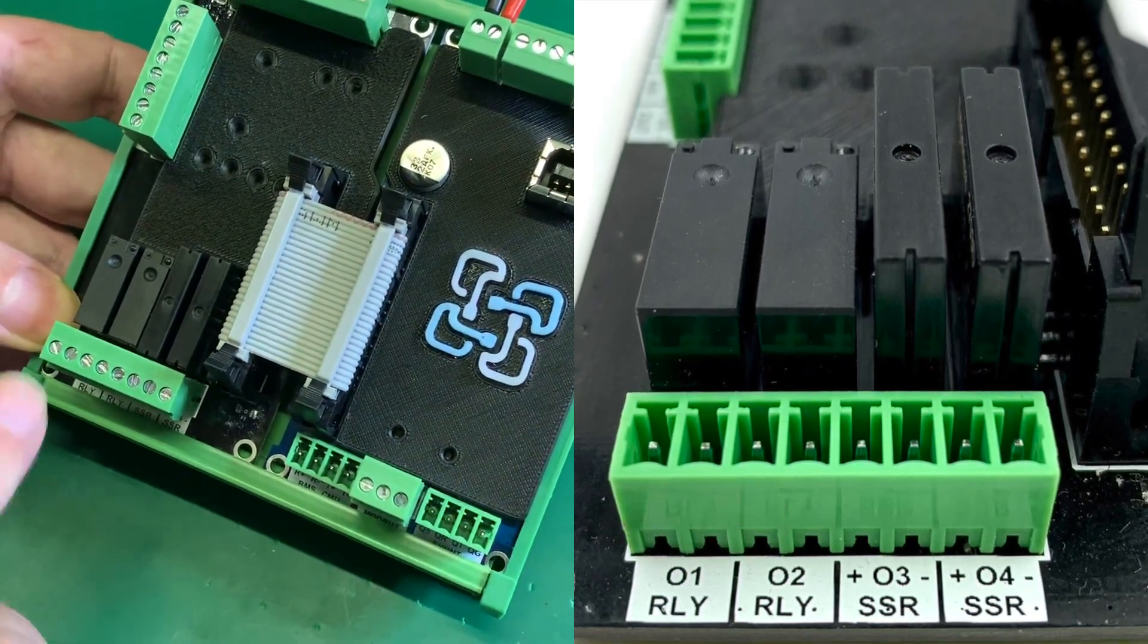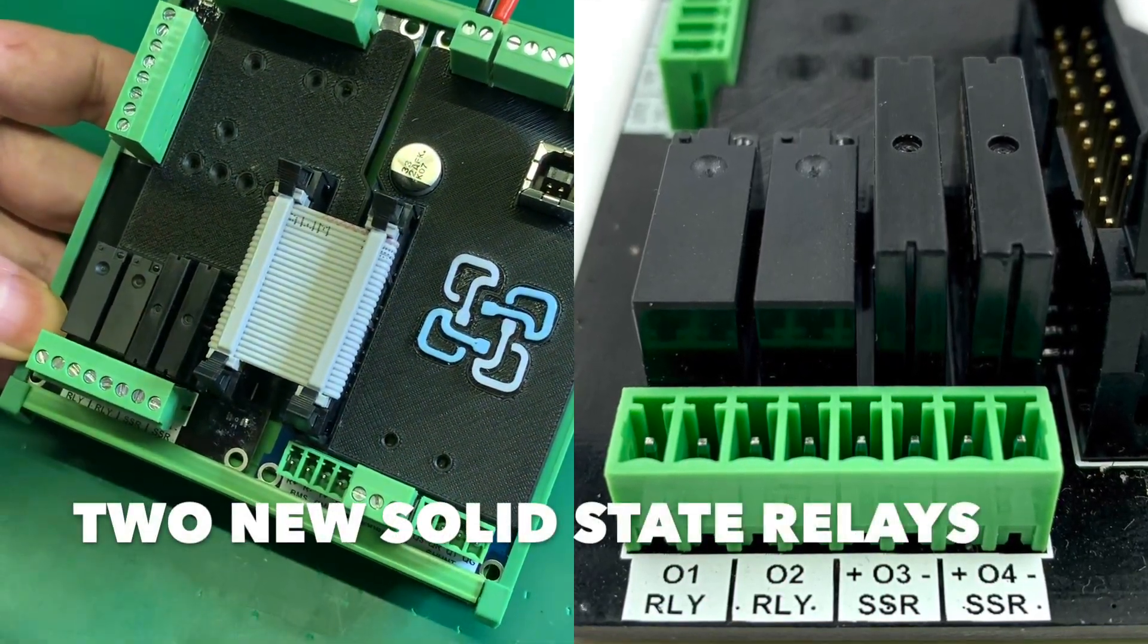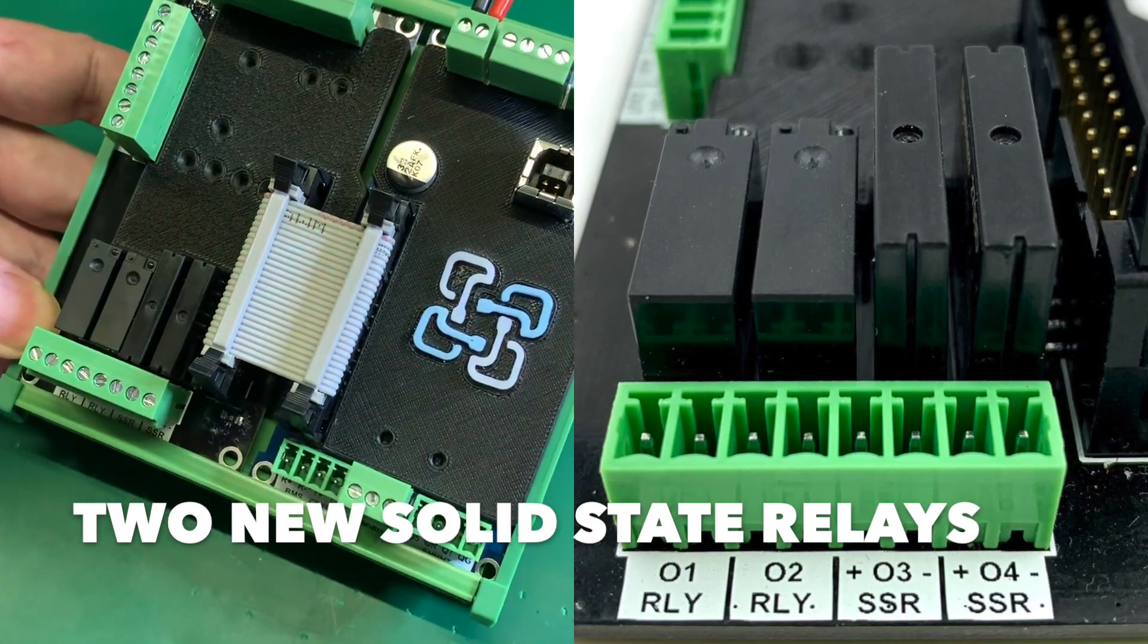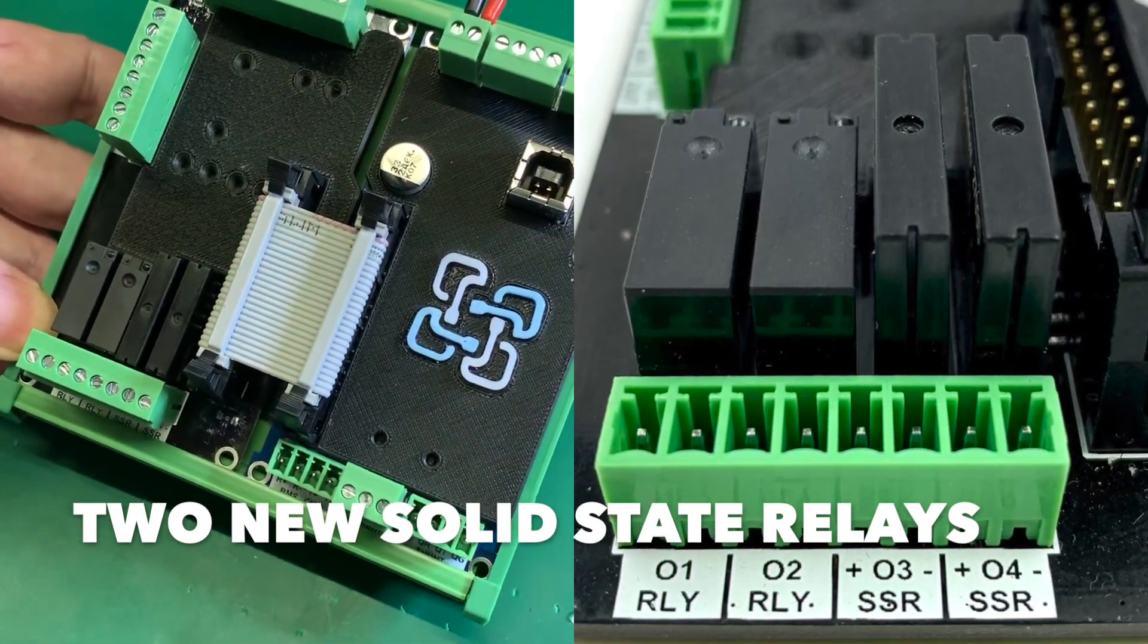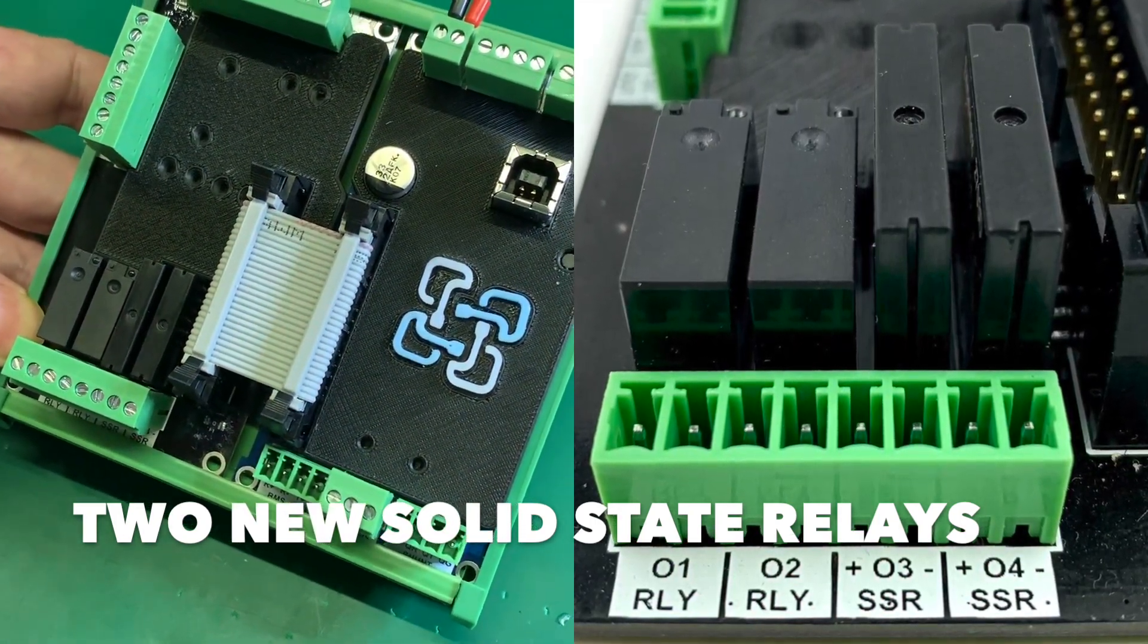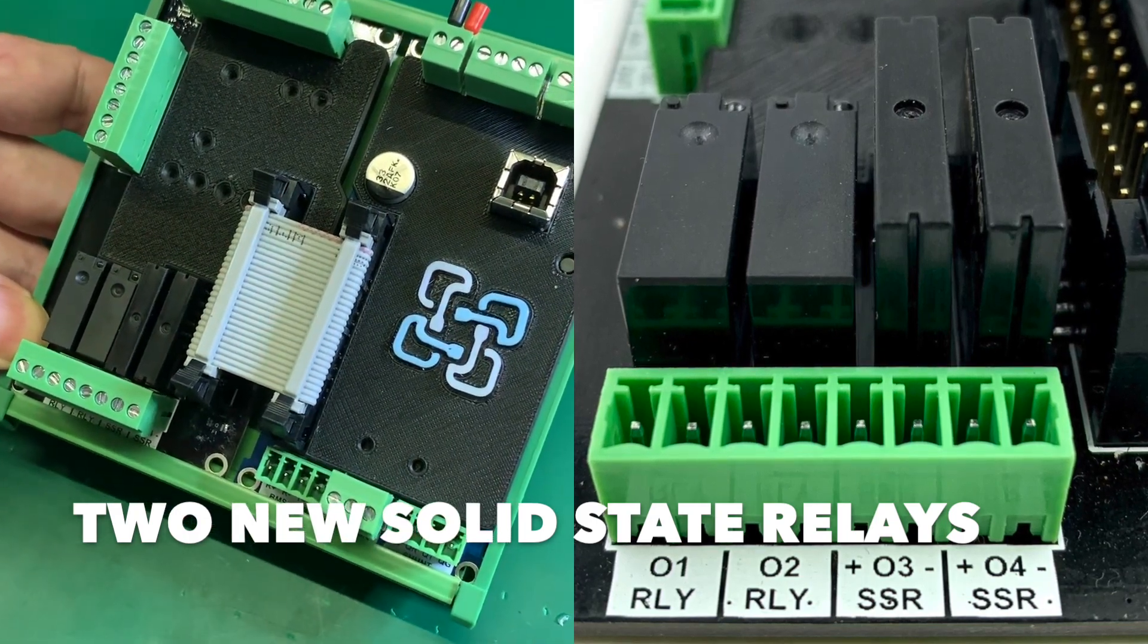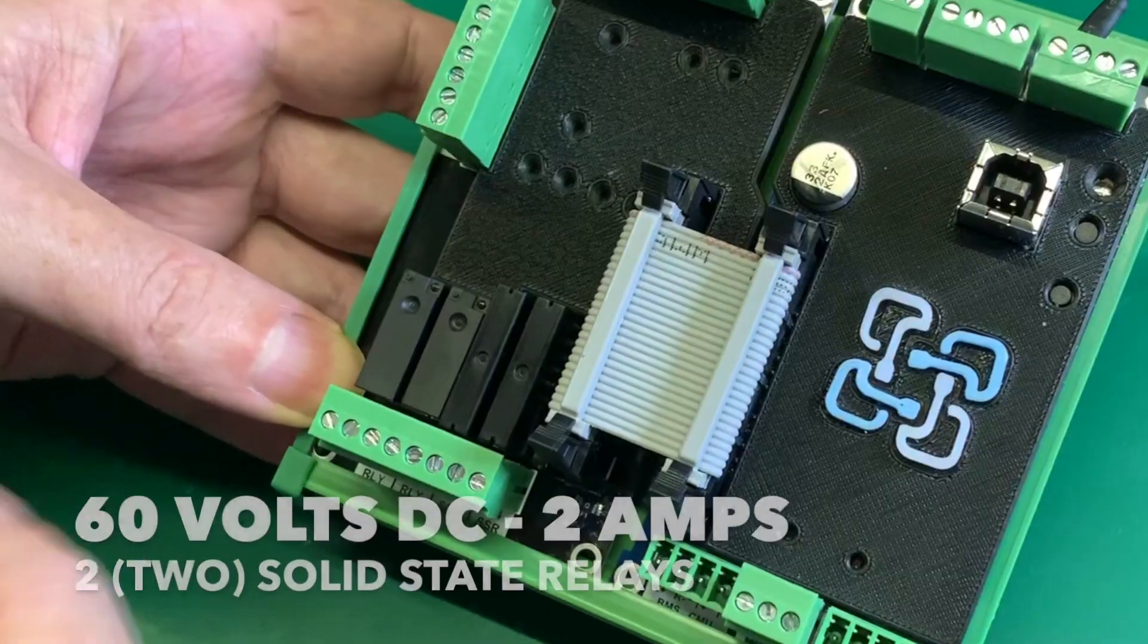We've now swapped out the mechanical relays for 3 and 4 for solid state relays. Why have we done that? Solid state relays have an advantage over a mechanical one. Firstly, they're able to switch on and off without any fatigue, so there's no mechanical failure.